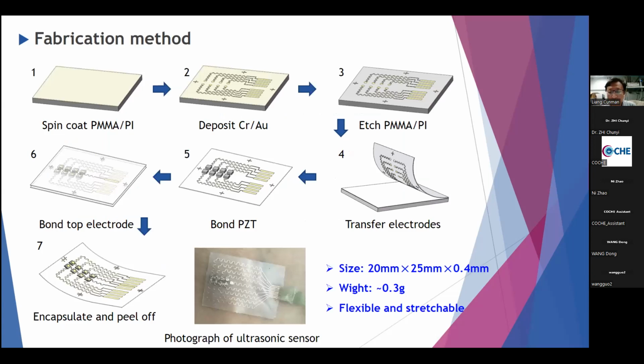This slide shows the fabrication process. Here, multi-step transfer printing is used to integrate the top and bottom electrodes. The total size of the sensor array is 20 by 25 millimeter, and the thickness is less than 0.4 millimeter. The weight of the device is less than 0.3 gram. The entire device is encapsulated with silicone rubber to ensure it is flexible and stretchable so that it can be attached to the skin.